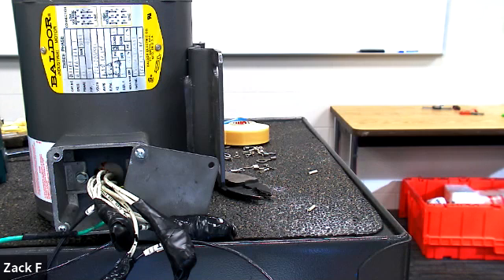This section right here, do you think the amount of resistance from this point to this point would be the same or different as from this point to this point? Very similar. So all those motor windings are about the same length. If they weren't, you wouldn't be getting consistent rotation, consistent force going around 360 degrees. So that's a key thing to keep in mind when troubleshooting motors. You can take resistance readings and compare them between each set.